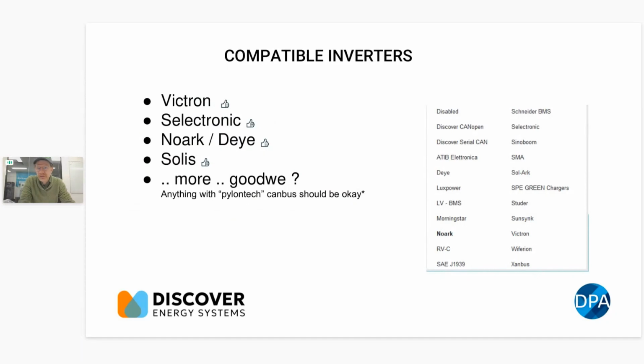It doesn't have an official compatibility with GoodWe, but basically anything that uses the PylonTech CAN bus protocol will work, because the inverter isn't testing to see which battery it is - it's just being sent voltage, current, discharge rate, charge rate, temperature, and errors. So as long as it's being sent those in the correct format, it will work. I know one person has used it with GoodWe, but it's not a supported integration - a power source is a power source. You can also run it open loop, so you could do that with SMA and things like that, but again it's not an official integration with those. All the ones we sell - Victron, Selectronic, Noark, and Deye - have nice integration, and we've got nice integration guides for all that.